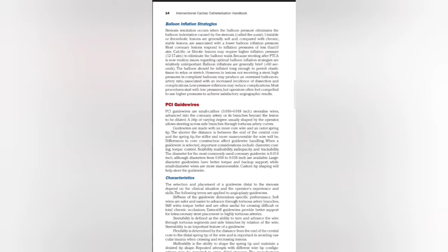PCI guide wires are small caliber, 0.010 to 0.018 inch, steerable wires advanced into the coronary artery or its branches beyond the lesion to be dilated. A J tip of varying degree, usually shaped by the operator, allows steering across side branches through tortuous artery curves. Guide wires are made with an inner core wire and an outer spring tip. The shorter the distance between the end of the central core and the spring tip, the stiffer and more maneuverable the wire will be. Differences in core construction affect guide wire handling.